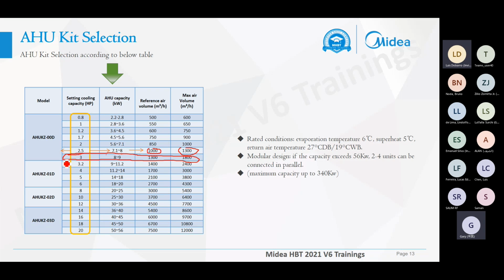When we select the AHU and set the cooling capacity, we should follow the range of the air volume and the AHU capacities. This table should be as follows. And the capacity rating condition is 27 degrees dry bulb and 19 degrees wet bulb. And the rating condition of the evaporation temperature is 6 degrees and the superheat is 5 degrees.